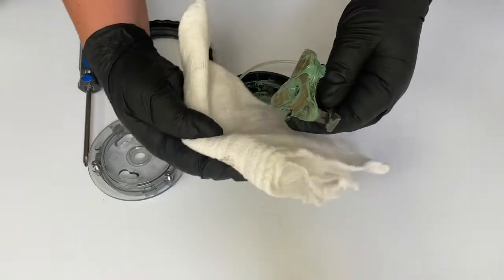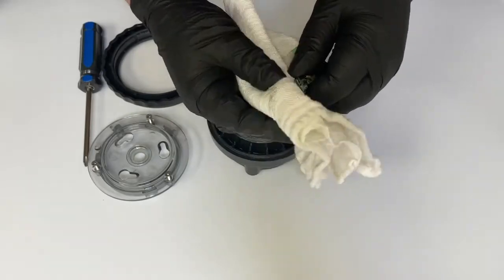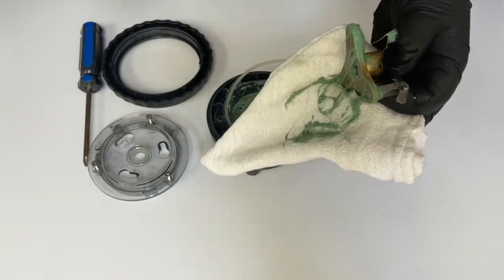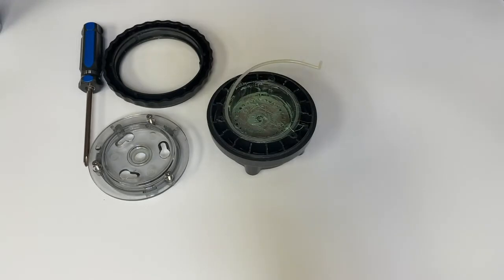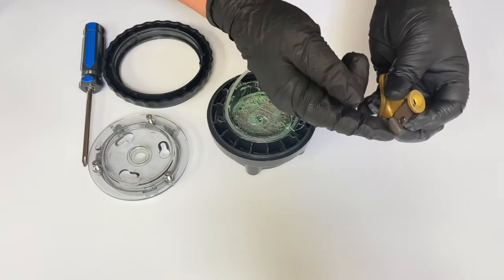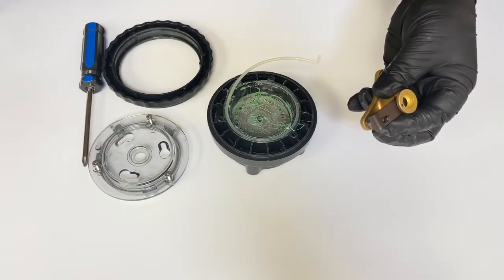Remove the brass spider and clean thoroughly with degreaser. Inspect the lifter, the tip should be slightly rounded. If the tip is flat, replace it.